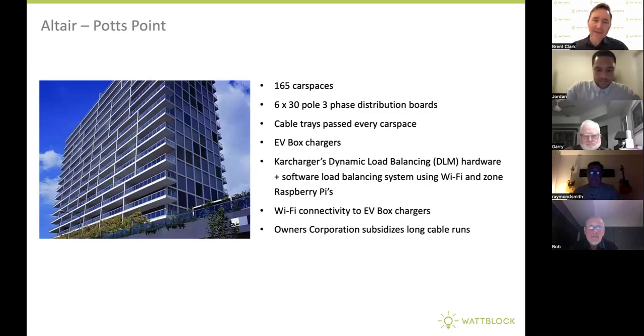That's because if someone is right next to one of those new distribution boards, the cable run might be 3 meters. If they're at the other end of the car park, it might be 60 meters away, and copper is getting more and more expensive. The difference for installing a charge point could vary from $1,500 of cabling and labor to $6,000, before you even pay for your charge point, depending on the cable run distance.